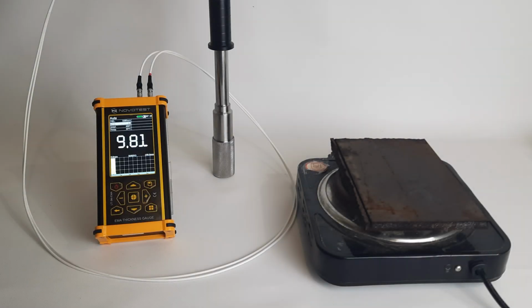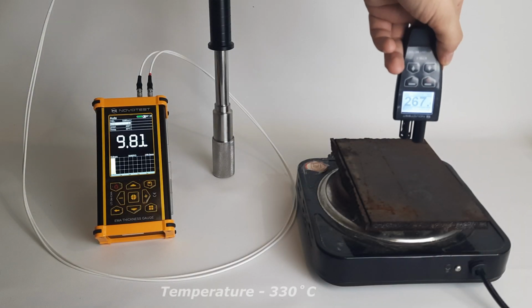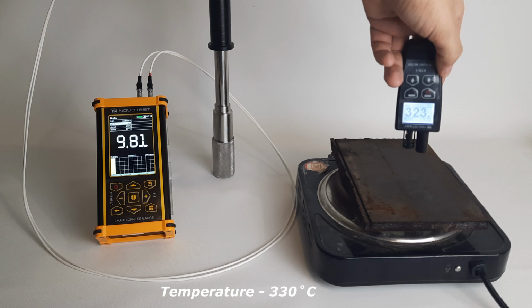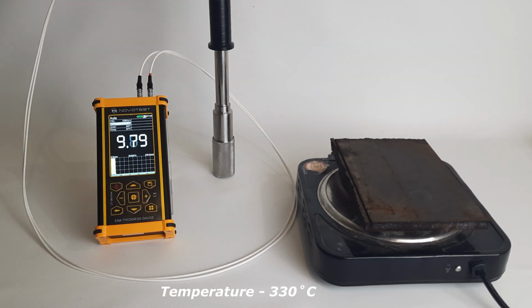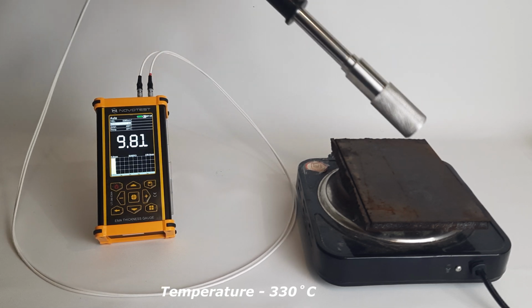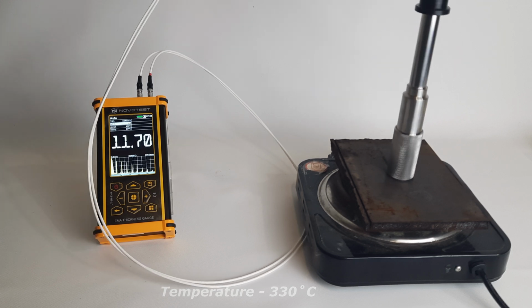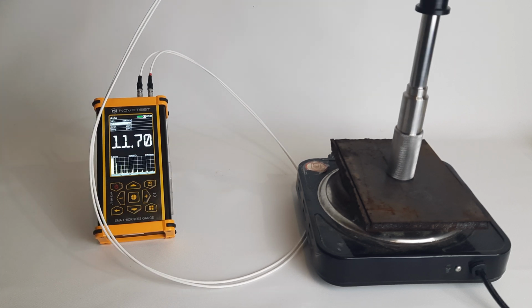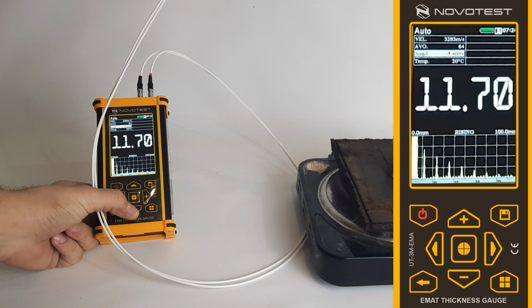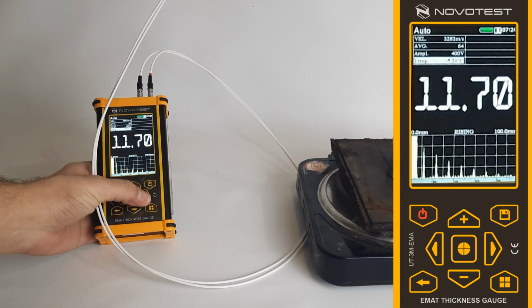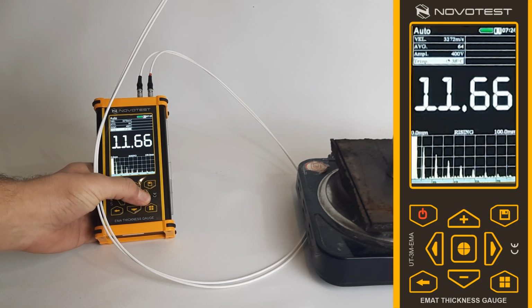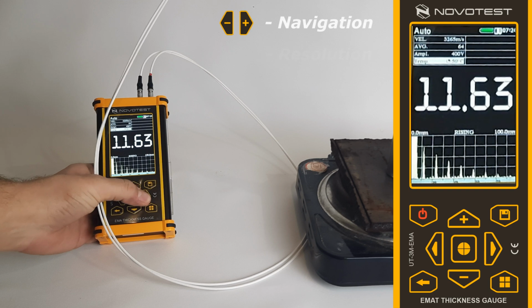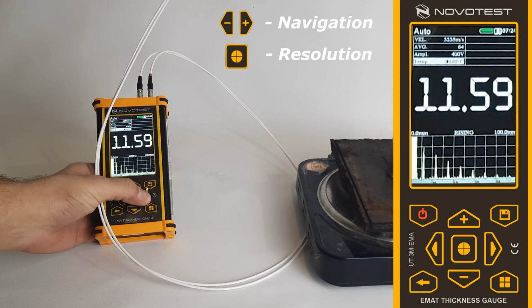But our EMAT thickness gauge can compensate for the temperature shift and display the most accurate measurement for any temperature of the surface. So to receive correct thickness for 400 degrees, for example, the operator should firstly calibrate the device at room temperature on the same material with the same velocity. After that, the operator can input the required temperature in the device's main menu using navigation and resolution buttons.